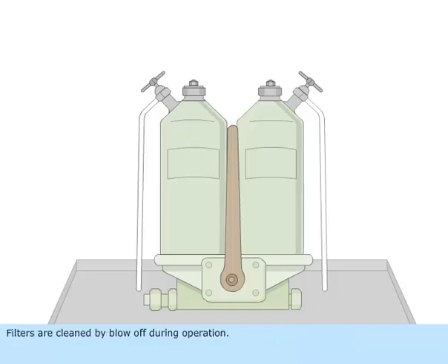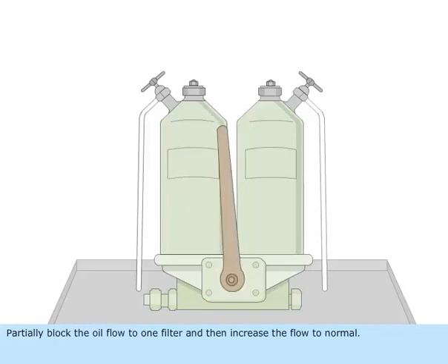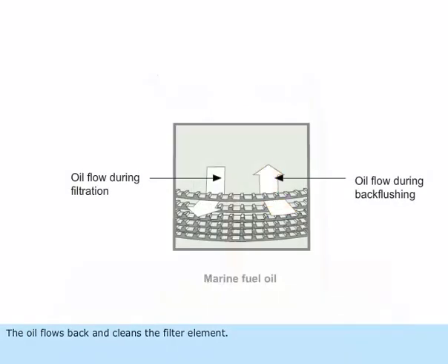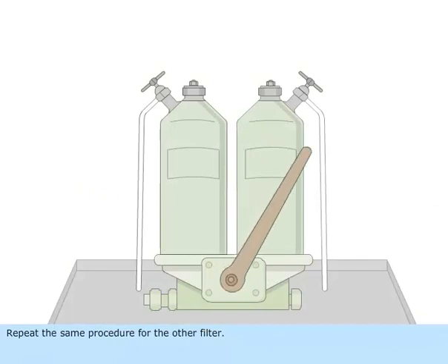Filters are cleaned by blow-off during operation. Blow off one filter at a time. Partially block the oil flow to one filter and then increase the flow to normal. The oil flows back and cleans the filter element. Repeat the same procedure for the other filter.